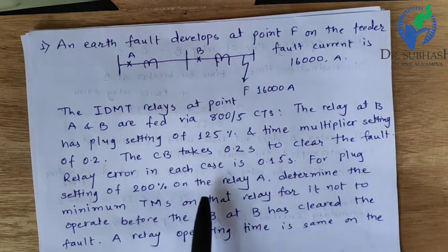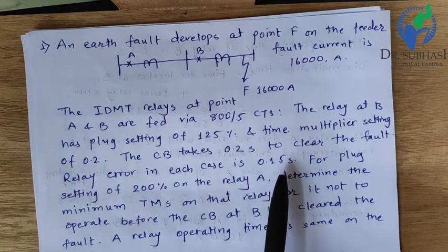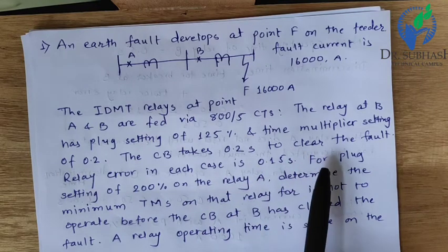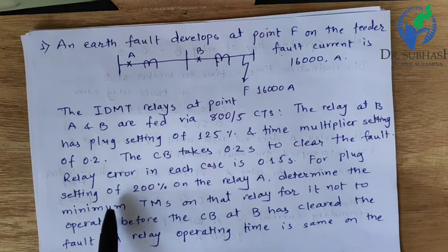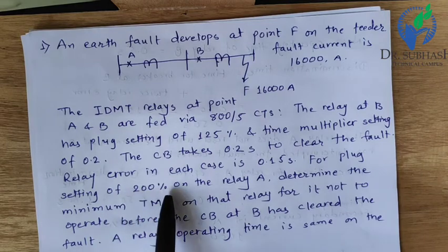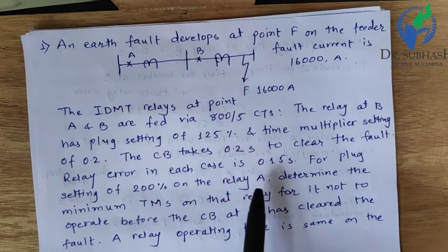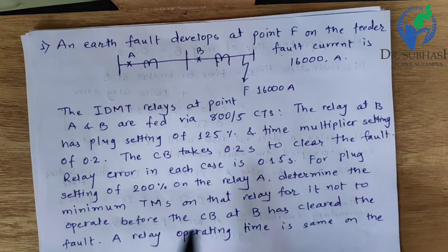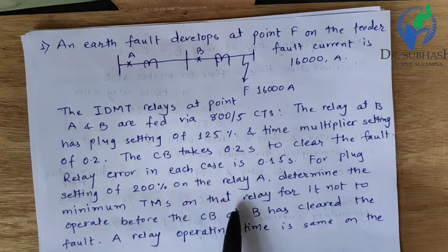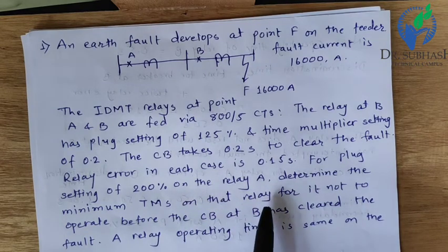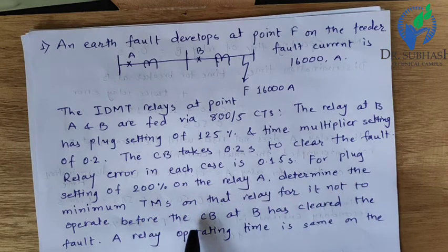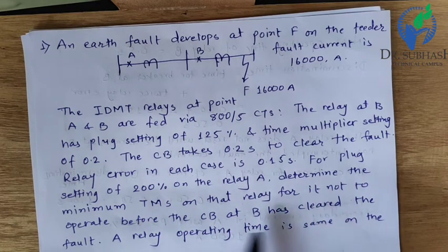Relay error in each case is 0.15 seconds. For Plug Setting of 200% on relay A, we have to determine the minimum Time Multiplier Setting on the relay for it not to operate before the CB at B has cleared the fault.